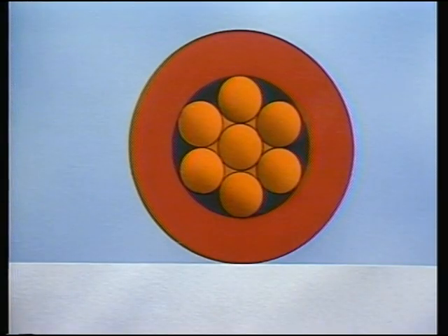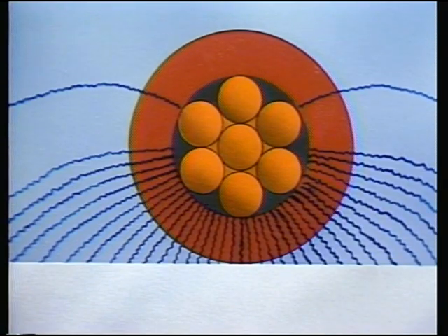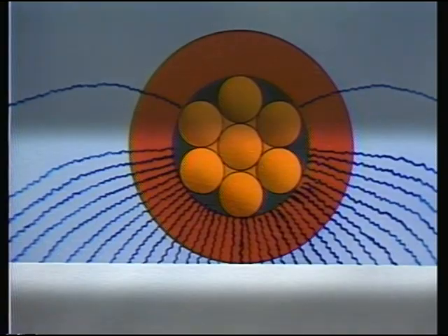But although the semiconductor shield layer provides a uniform thickness around the conductor, it does not completely reduce the voltage stress concentration through the cable's insulation layer. These lines, bending toward ground potential, show that voltage stress is still present, but that it is now concentrated in the area of insulation closest to ground.